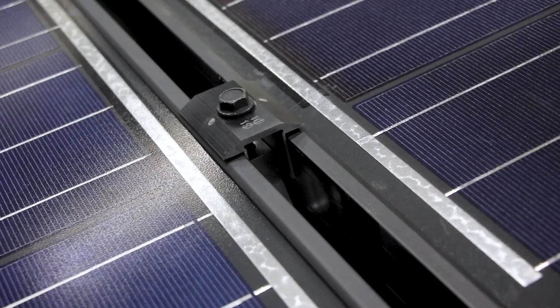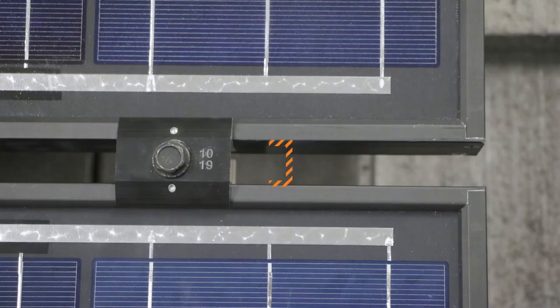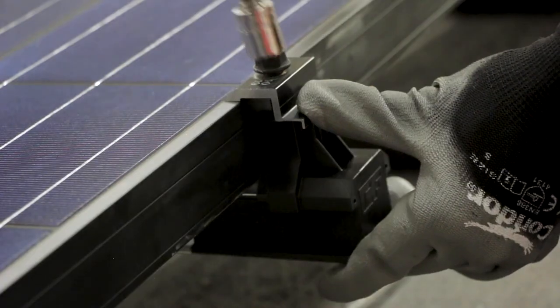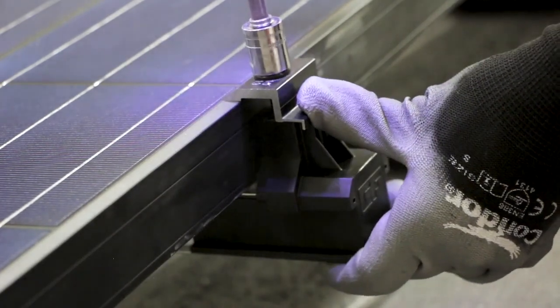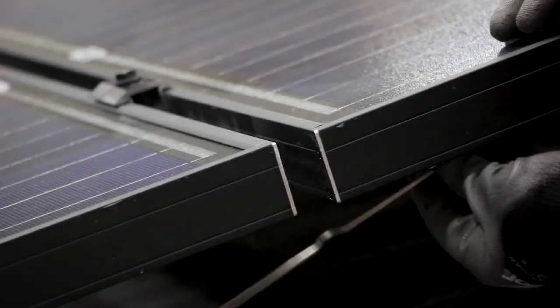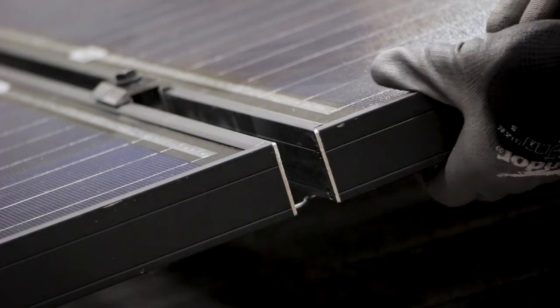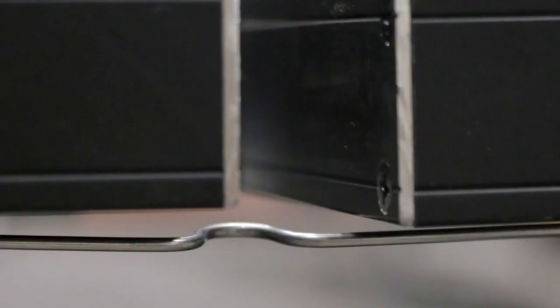Repeat the process for installing the first module in the next row. Temporarily place a mid clamp between the north-south gap between the modules and slide the first module in the row up to this mid clamp to achieve the proper 3/4 inch spacing between rows. Then secure the module into place by tightening down the end clamp. It's a good idea to install the bonding jumper to this first module or to the last module in the row.